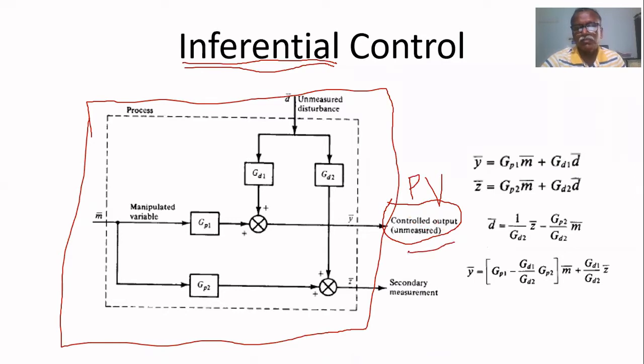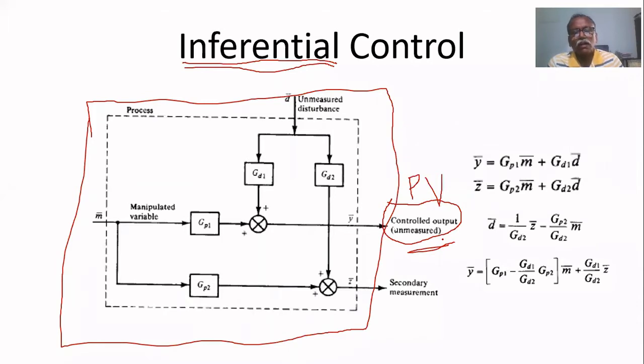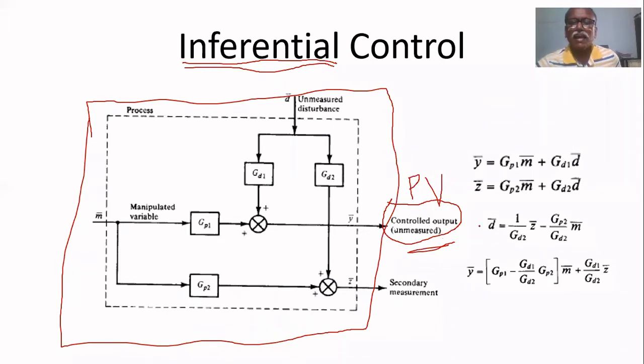For example, consider reflux ratio control. Yesterday we saw that the purpose of reflux ratio is to improve the quality of the top product. But it is not possible to measure the quality of the top product online. We have to do it offline — take a sample and measure it in the lab to get the purity. So if we want to maintain the quality, we have to go for inferential control. That is why we indirectly control the temperature in reflux ratio control.